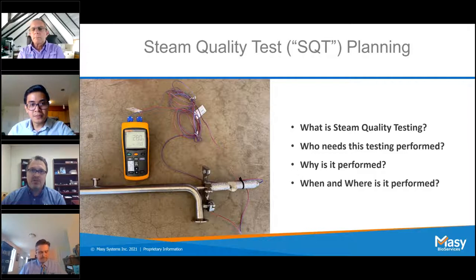The second test that we do is for superheat. We're making sure that the steam is at an appropriate temperature above its boiling point at a given pressure. We want that steam to actually phase change and condense when it's entering the sterilization environment. If the temperature is in excess of what it should be, superheat will interfere with that being done effectively. Superheat can also be produced as a result of an excessive pressure drop. So there's a criterion there that we want to make sure the steam will meet.